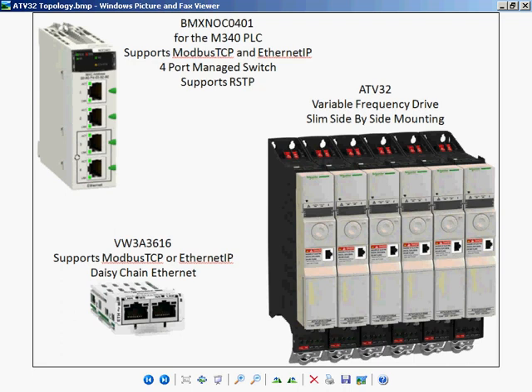We'll demonstrate how to configure the communication parameters of our ATV32 to be controlled over Modbus TCP communications. First, the hardware. You'll need an ATV32 and the Ethernet module that plugs into it. Our Ethernet module supports Modbus TCP and Ethernet IP and has two ports for daisy-chaining your Ethernet.